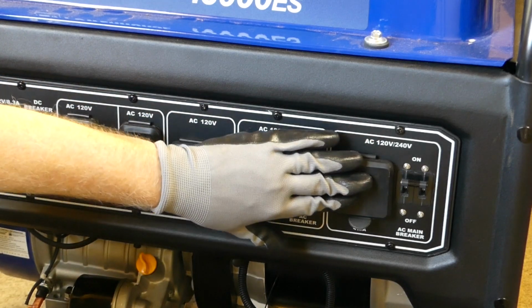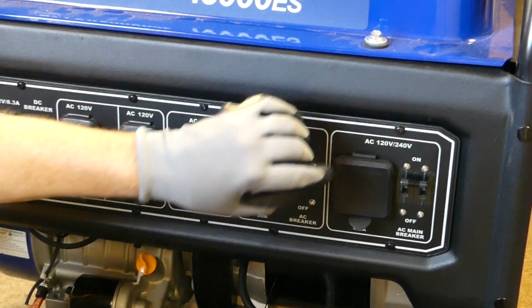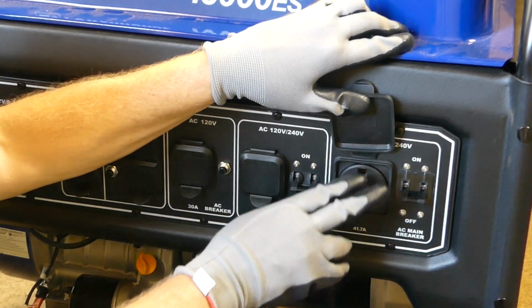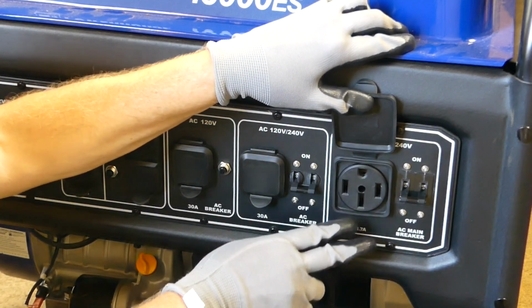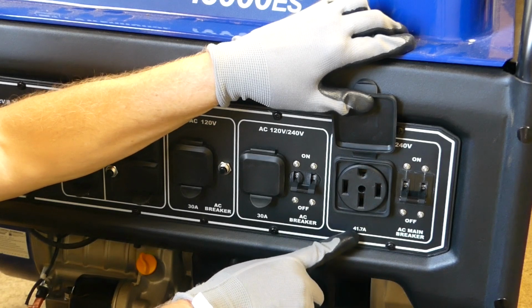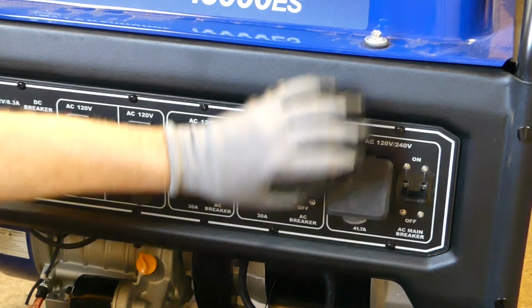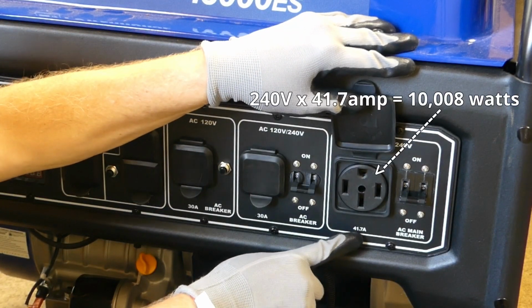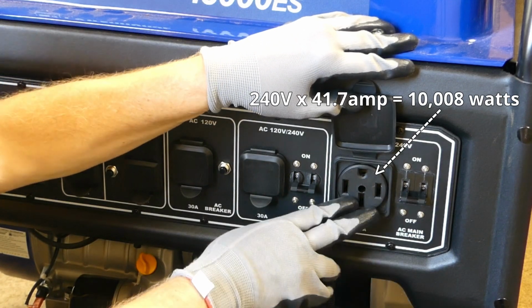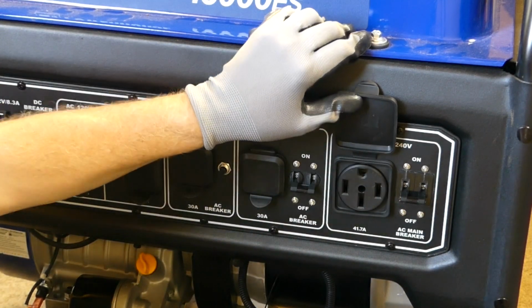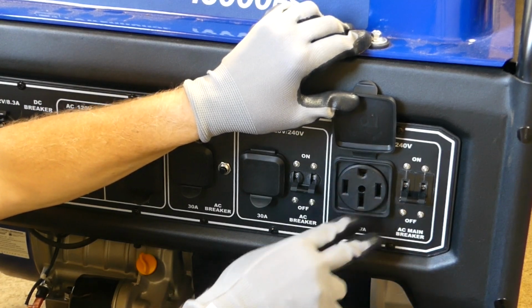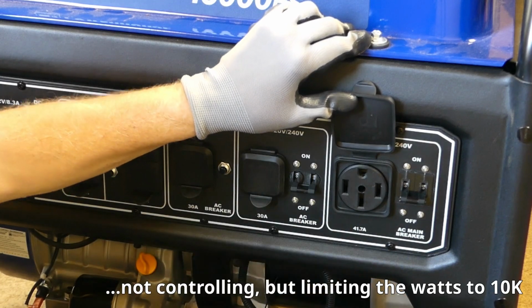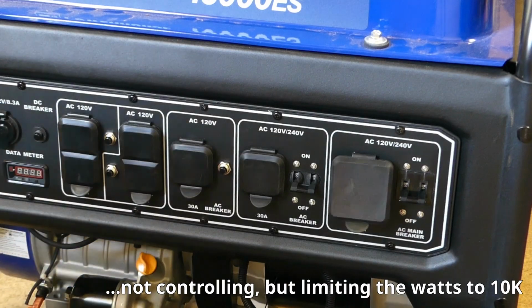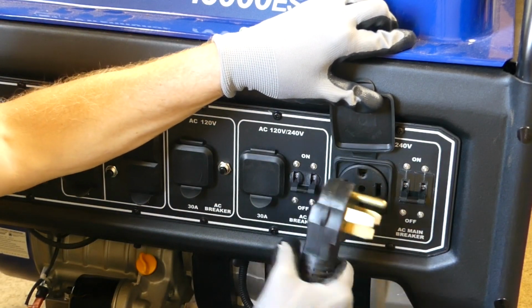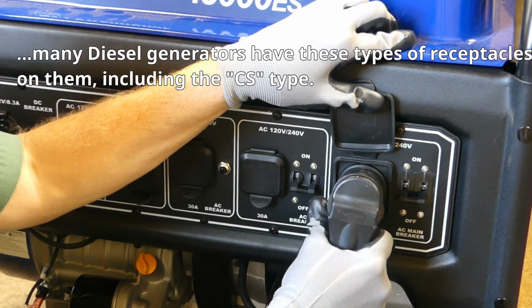Okay, the last receptacle on this is 120/240 volt, and this is a 50 amp service receptacle. Now, for this particular receptacle, they're showing that it is restricted to 41.7 amps. So if we take our 240 volts times our 41.7 amp breaker, we come up with 10,000 watts. This is what the whole generator can produce continuously. So even though it's a 50 amp style receptacle, the breaker is what's controlling the wattage coming out of the generator. And these types of connectors require these types of plugs.